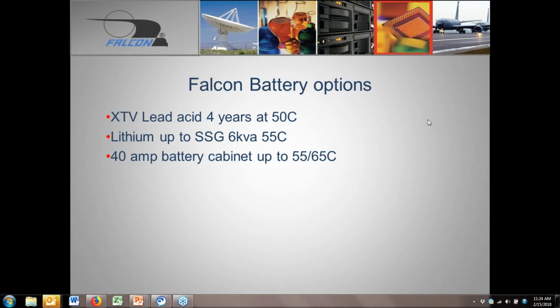The beauty of the method of charging for our systems is that it requires very low maintenance. The charge current is such that it won't put a large bearing on the batteries. Any discharging cycles that may be produced every 6 months, a year, whatever time frame is available, would be a normal part of preventative maintenance for any equipment, really. But it doesn't require any short-term scheduling to have those batteries in top shape. They are, for the most part, maintenance-free as far as the packs go, and the UPS charger will take care of that.